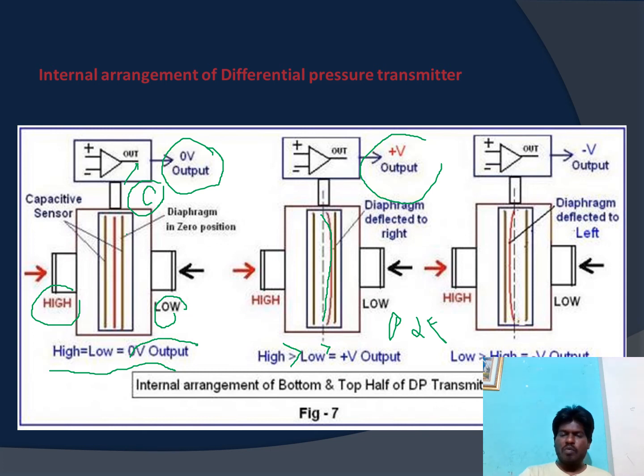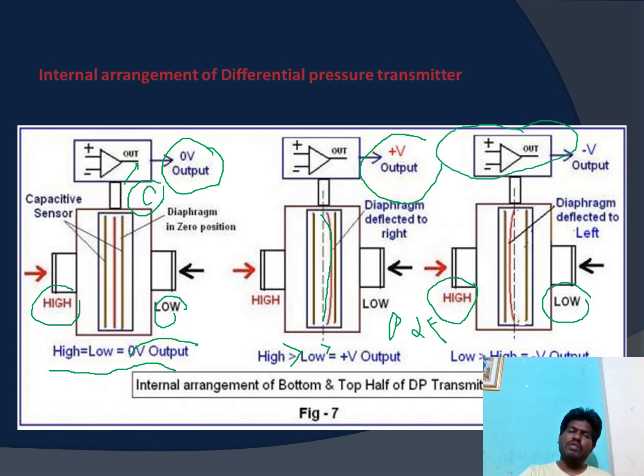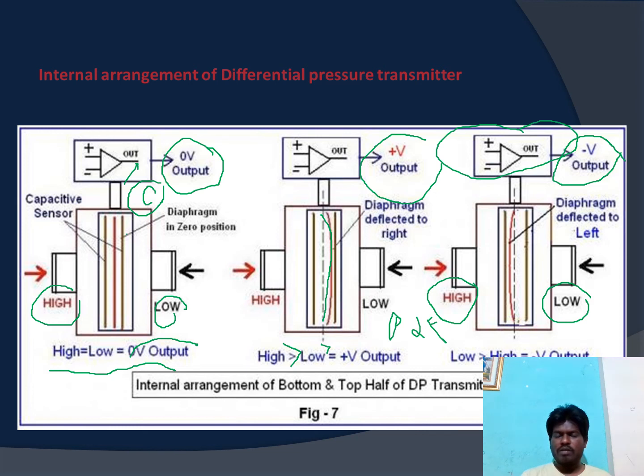In the third condition, the operation is the opposite. The diaphragm moves towards the left-hand side because the low pressure terminal is having higher pressure than the high pressure terminal. The distance between the two capacitor plates changes, which changes the capacitance, and this capacitance output goes to the signal conditioning circuit. The resulting output is a negative voltage, clearly indicating that the low pressure end is having higher pressure than the high pressure terminal.